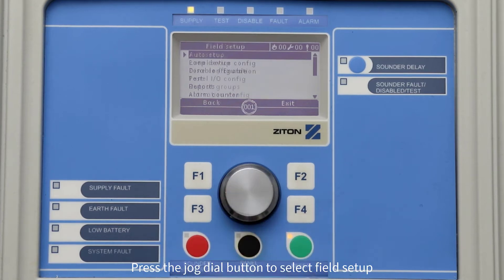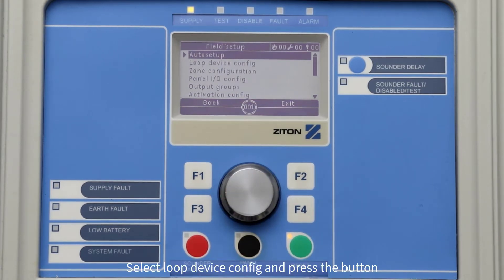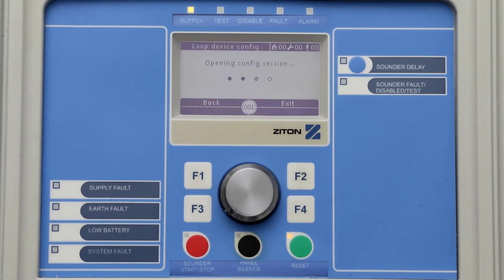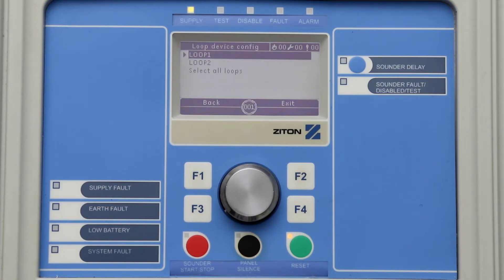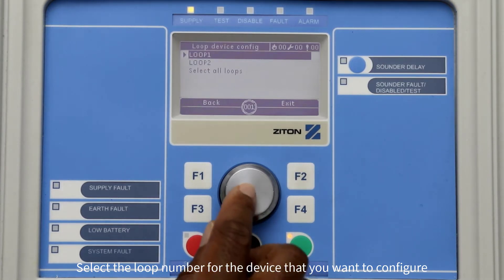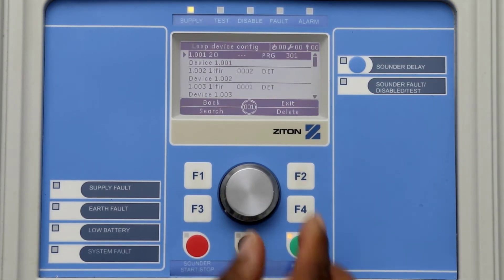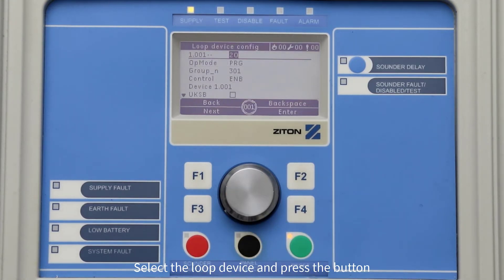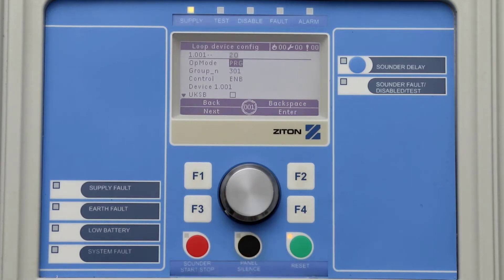Press the jog dial button to select Field Setup. Turn the jog dial button and select Loop Device Config, then press the jog dial button. Select the loop number of the device that you want to change its credentials for — in this example, loop number one. Turn the jog dial button until you find the relay that you want to configure, then press the jog dial button. Press F3 or press the jog dial button to select Next.